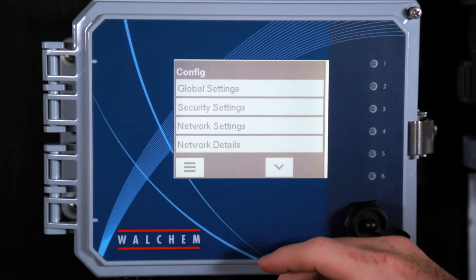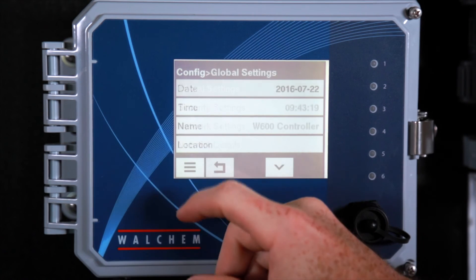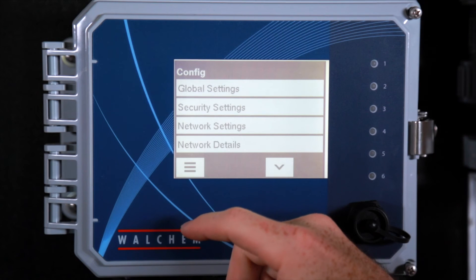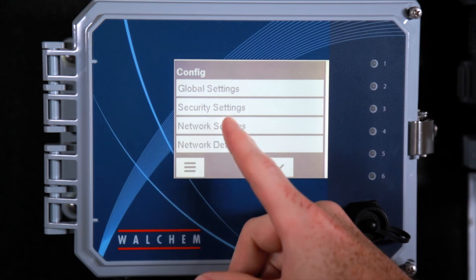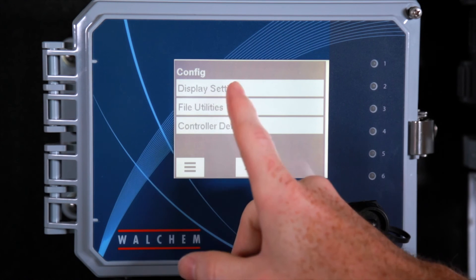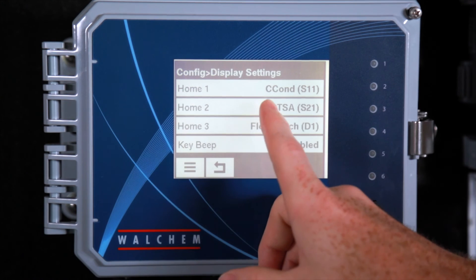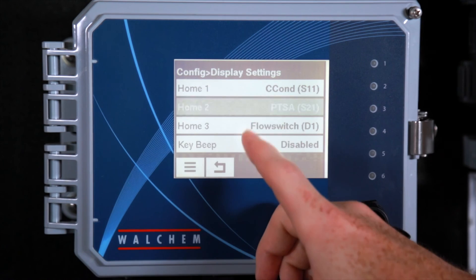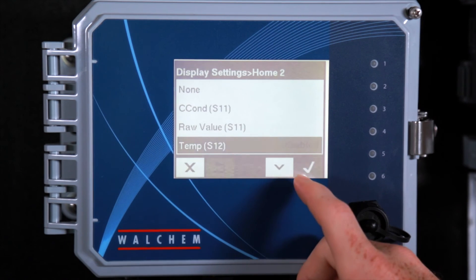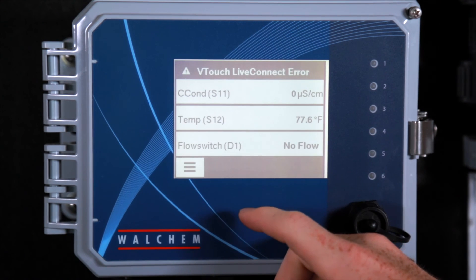Right here is your config menu — this is where you would set up the controller settings. First we've got the global settings: that's going to be your time and date, name of the controller. Your security settings is where you would set up a password for the controller. Your network settings are your Ethernet settings. Then you've got your display settings, where you can set up which sensors you want displayed on the screen. Right now we've got conductivity, PTSA, and flow switch. If you wanted to change one to temperature, you select temperature, hit check, and now when we go back to the home menu the display shows conductivity, temperature, and flow switch.